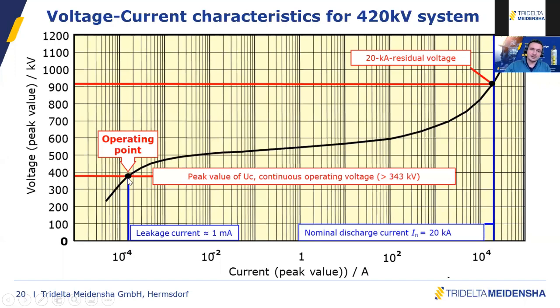Here is the Uc. This is the maximum continuous operating voltage. So basically, in real life, this point is always here, and the surge arrester can withstand this voltage across its service life. Sometimes, if you have a TOV value, you go up into this area for a few seconds, then it goes back to the operating point. And this is fine. But the surge arrester is actually used to limit overvoltages. So from time to time, you have a switching or a lightning impulse, and you go very quickly, a few microseconds, into this area. And you want to make sure that you don't exceed the BIL of your system.